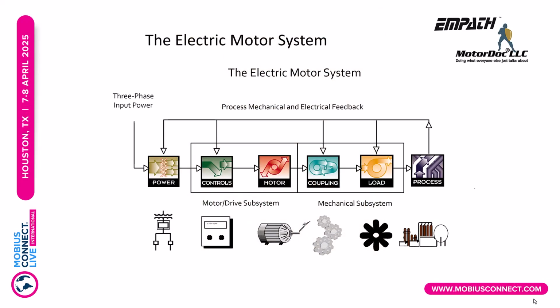The electric motor system consists of incoming power, and basically this is the supply to a control, whether that's a cross-the-line starter, VFD, soft start, whatever it is, to an electric motor through a coupling to the load and the driven equipment or process. Through this, there can be different things. Like if there's a VFD, that's going to be a wall for anything we're doing. But whether there's a VFD or a straight power supply, we're going to worry about things like power quality and so on. In the electric motor, you have your electrical and mechanical components, including insulation systems.